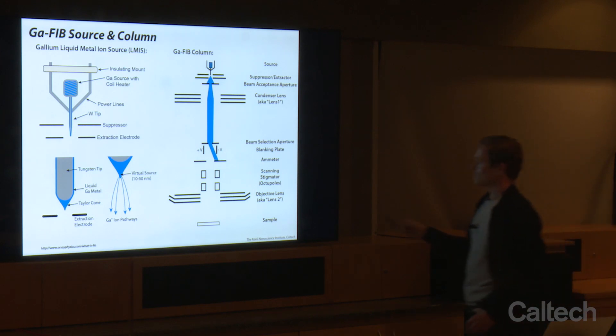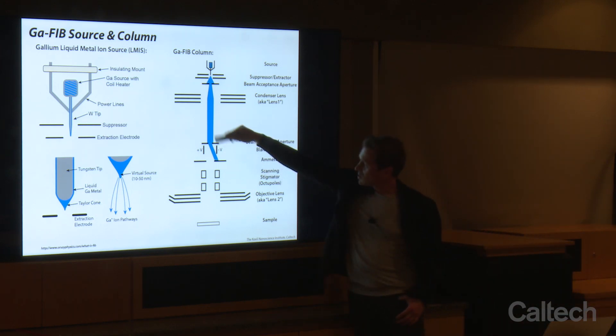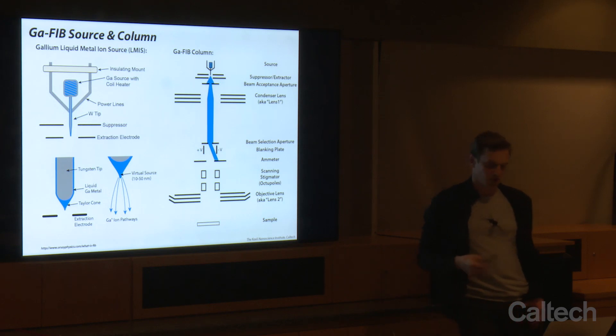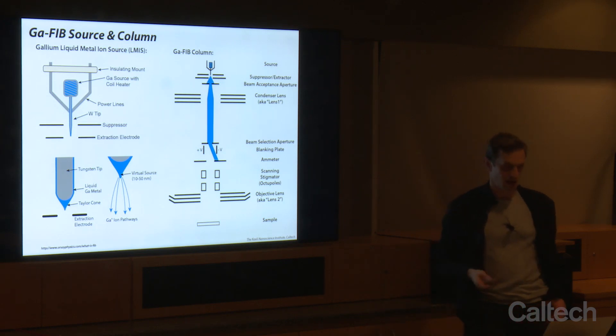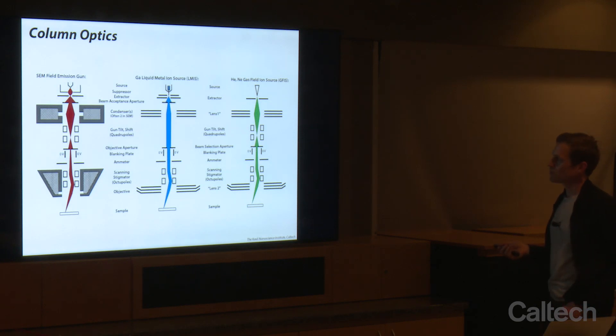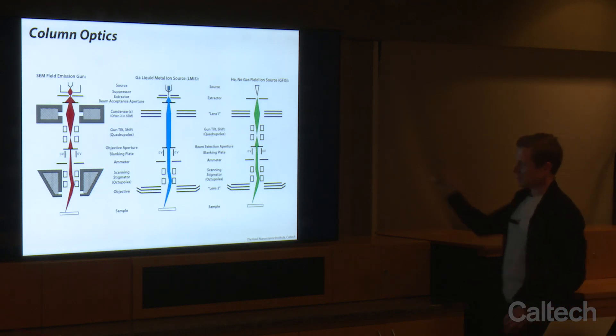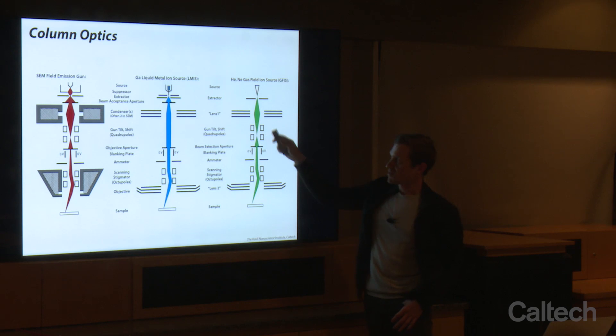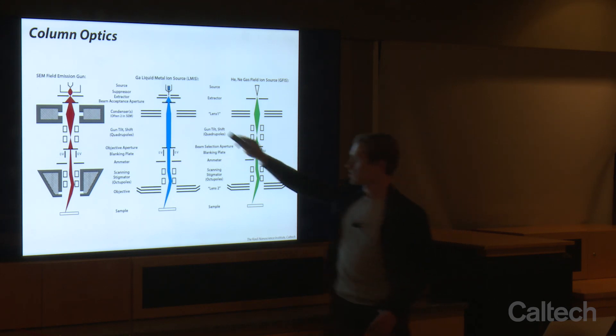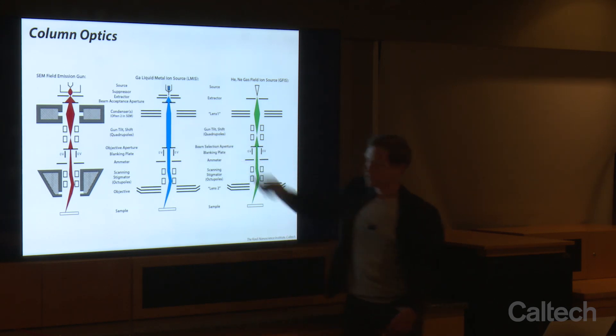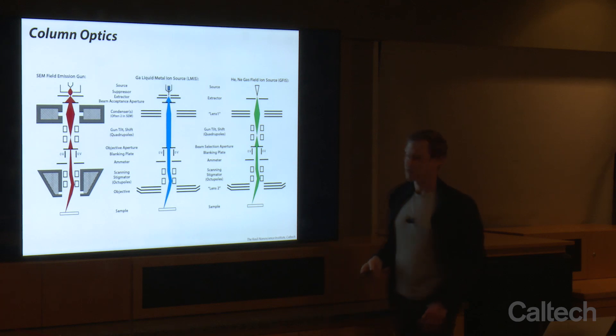We can apply a voltage to the blanking plate and direct the beam onto an ammeter to measure the current in our beam. And as I said, we can look at the optics of the three different types of microscopes — the only thing missing in the gallium-focused ion beam system are the steering optics.